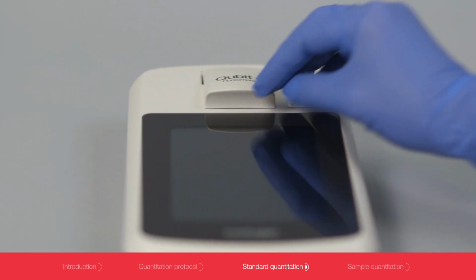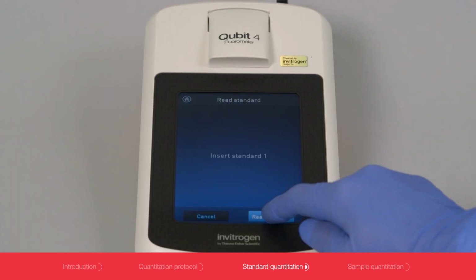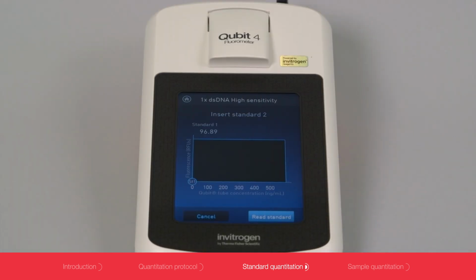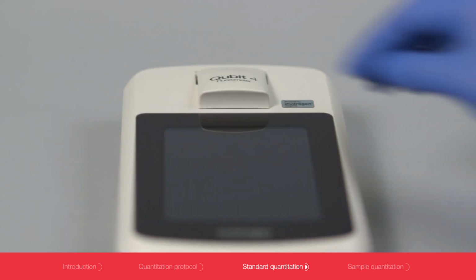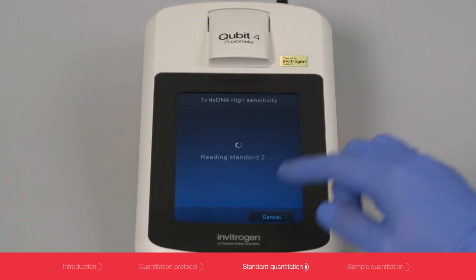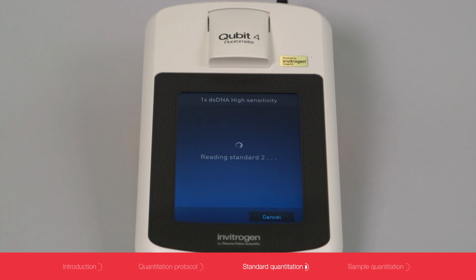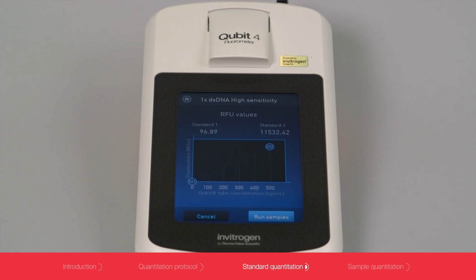You will then follow the on-screen prompt to enter Standard 1, followed by Standard 2. It takes about 3 seconds per read, and the value of each standard is displayed on the graph. The two values refer to the actual fluorescence values. These values are important for troubleshooting.